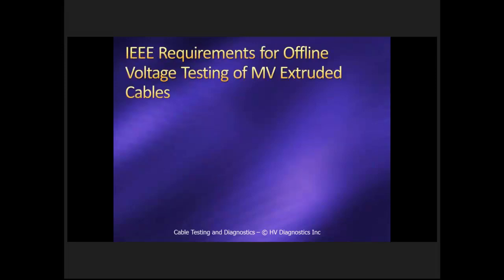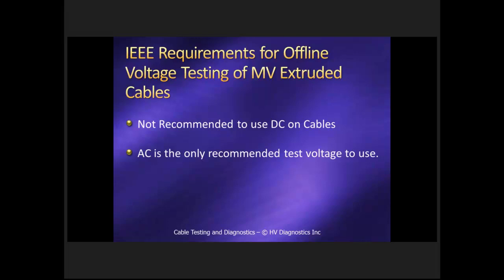IEEE requirements for offline testing: it is not recommended to use DC on extruded cables. There is a standard for testing with DC on laminated cables like paper lead, but again, a large part of what we test is not paper lead. AC is the only recommended test voltage to use, and that applies to partial discharge. Even if we could use DC on the cables, we wouldn't be using DC to do a partial discharge test on them in any case.